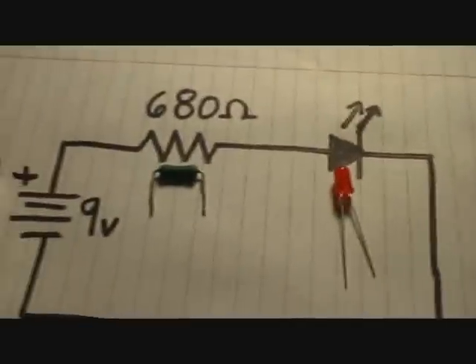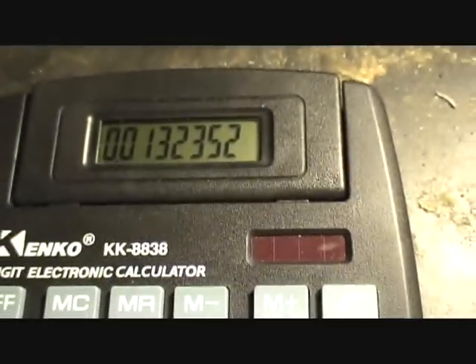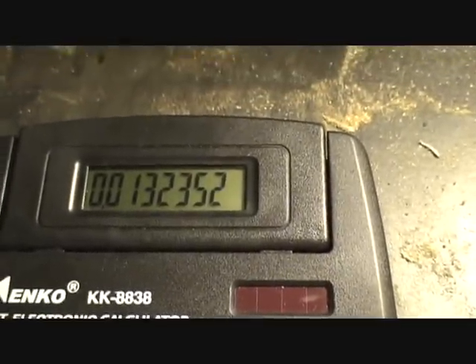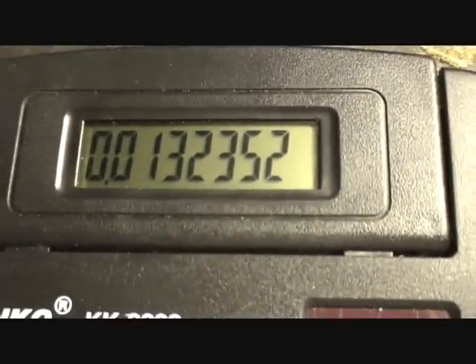In this case, it's gonna be 9 volts over 680 ohms equals that. Alright, so I punched in the calculator and what we got is 13.2 milliamps, which isn't over 50, so we should be good.